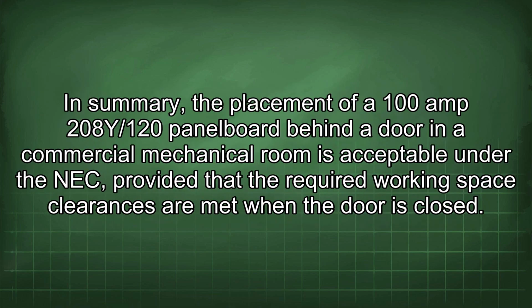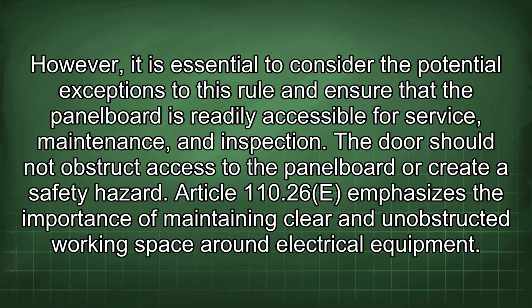In summary, the placement of a 100 amp 208Y/120 panel board behind a door in a commercial mechanical room is acceptable under the NEC, provided that the required working space clearances are met when the door is closed. However, it is essential to consider the potential exceptions to this rule and ensure that the panel board is readily accessible for service, maintenance, and inspection. The door should not obstruct access to the panel board or create a safety hazard.